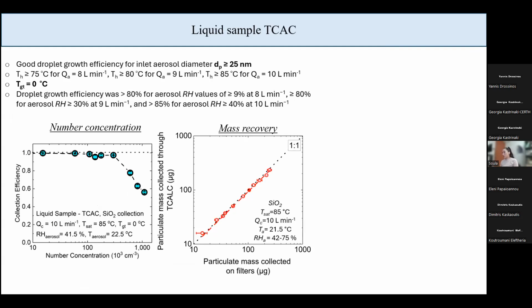I did the same characterization as before. I saw that I was able to collect particle sizes down to 25 nanometers effectively. I tested it for 3 different flow rates, 8, 9, and 10 liters per minute. The optimum temperature of water was different for each flow rate. The growth tube temperature was at 0 degrees Celsius at all times, because this is where we were getting the best results. And I also found the optimum RH range for each aerosol flow rate that I used.